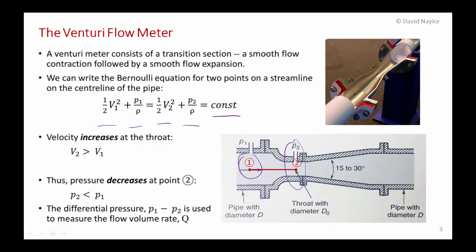Because of continuity and conservation of mass, when you reduce the diameter of the pipe the velocity increases, so the velocity at point two is greater than at point one. The kinetic energy in the flow goes up, and since kinetic energy plus pressure energy must equal a constant, the pressure has to decrease. So the pressure at two is actually lower than at one, and it's this differential pressure that we can use to measure the volume flow rate.